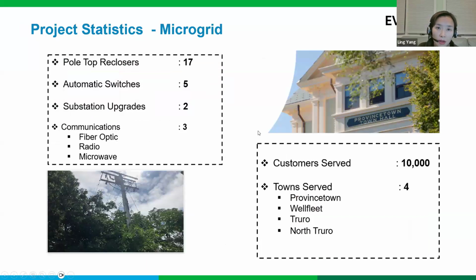Aside from the battery sites, we have done a lot of system upgrades along the distribution circuits, and we have installed new reclosers with automatic switches, and also we have done some substation upgrades. Under certain circumstances, we require the system to be tripped faster to avoid some system stability issues, as well as communication infrastructure upgrades in the area. In total, we serve around 10,000 customers along the distribution circuits for the battery interconnects.